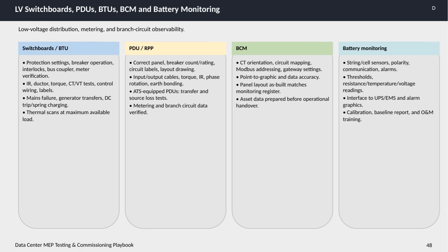Moving to power distribution units and remote power panels, the key checks include confirming correct panel specifications, breaker counts and ratings, and accurate circuit labeling. Input and output cables are inspected thoroughly, along with torque, insulation resistance, phase rotation, and earth bonding. For PDUs with automatic transfer switches, transfer tests and source loss tests are conducted to guarantee reliability.